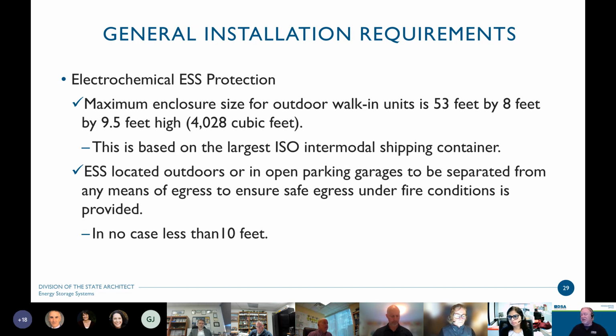Maximum enclosure size specified by code for these walk-in units is 53 by 8 by 9.5, a little over 4,000 cubic feet. So if we do end up in that alternative fire suppression design mode, we're going to be looking at the cubic volume of those containers and what kind of fire suppression agent, and the quantity of agent, that will be necessary to control an event. And you wonder where this size comes from. Well, it's pretty much based on the largest ISO intermodal shipping container that's out in the world right now.